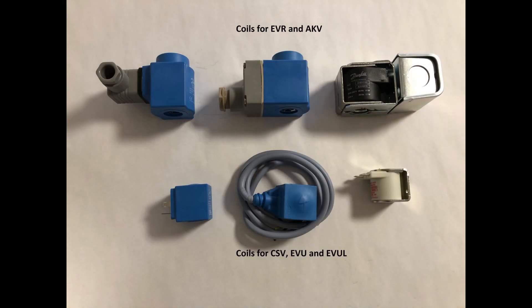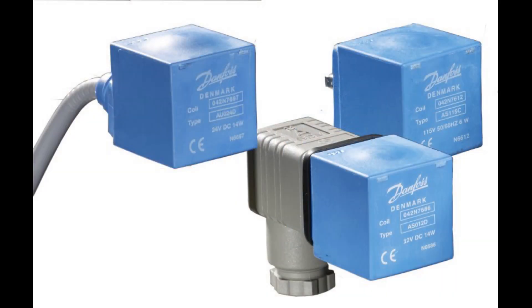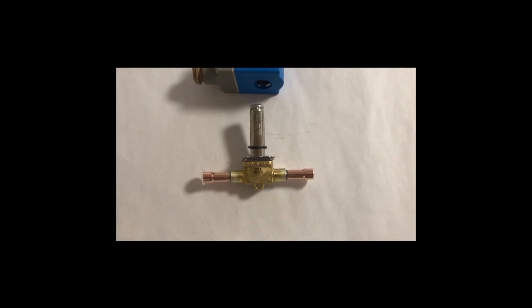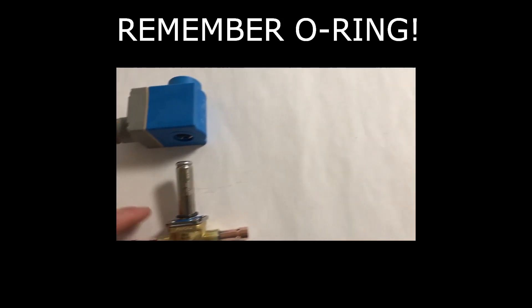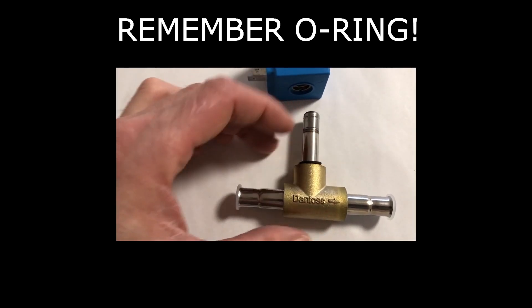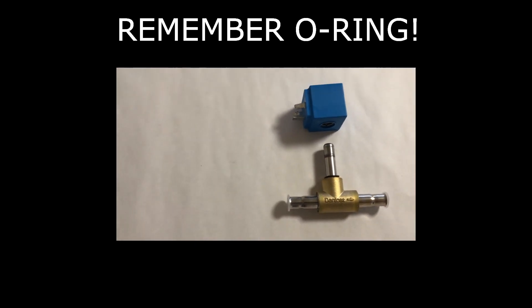Here you see different coil types and designs which can be used. Here the blue internal metal frame type — large size for EVR and AKV, and small size for CSV, EVU, and EVUL. For this coil type, it is very important to ensure a coil O-ring is mounted on the armature tube, like this, between valve and coil to prevent moist ingress between plastic and metal into the internal coil, since such moisture can cause coil short circuit and coil burnout.